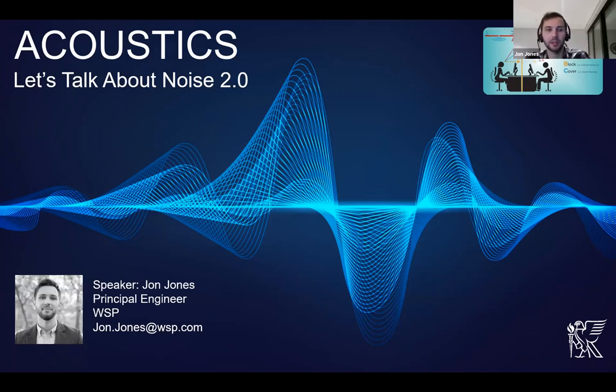Not really, in terms of the acoustic design, I suppose. I think that would probably be one for the mechanical engineer to consider. I might be proved wrong with a worked example, but my initial thoughts would be the face velocity wouldn't increase too significantly. And if it did, it's unlikely to be the difference between totally fine and totally wrong, essentially. But in terms of the noise, acoustically, there would be no difference. We'd get the acoustic benefit we're looking for from the internally lined ductwork. We'd only be looking at regenerated noise as a result of the increased flow rate, which I don't think would be changed significantly.